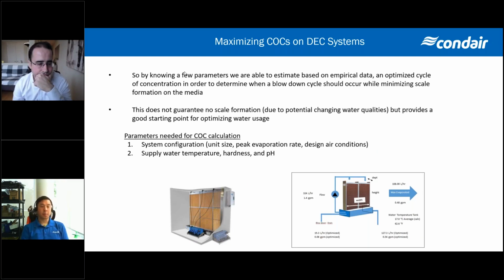So by knowing just a few parameters, based on some of the empirical data that we've gathered throughout the years and these systems running in the field, we've developed a way to try and calculate or optimize the cycles of concentration to determine when a blowdown should occur, to try and minimize scale buildup on that media and extend the life of the media while minimizing water consumption. By no means does this guarantee no scale formation on the media, again, really due to potentially changing water qualities or changes in the operation of the system throughout the year. But it does give us a very, very good starting point for looking at how we can optimize that water and setting up the system initially.